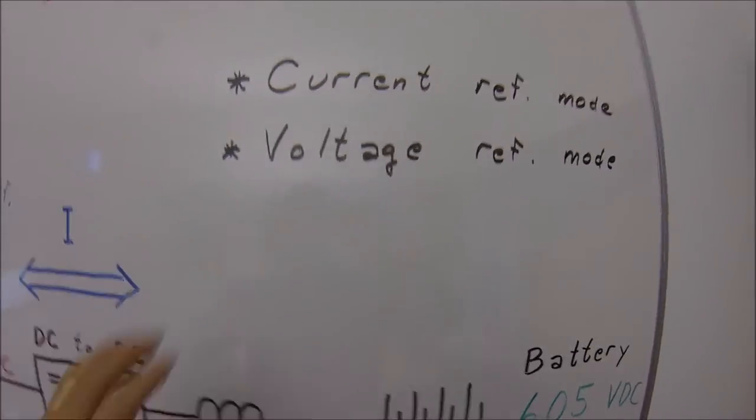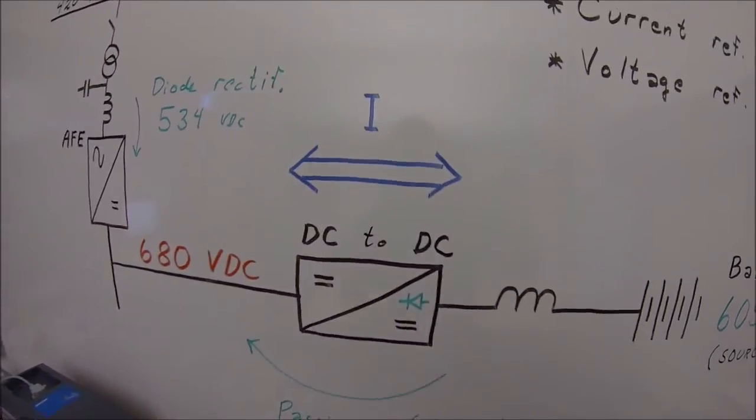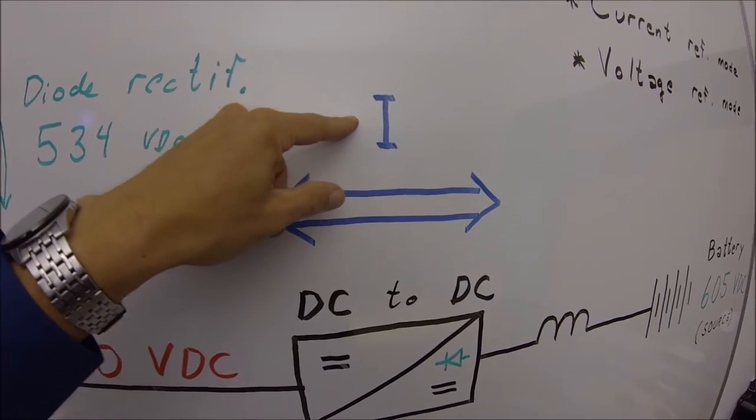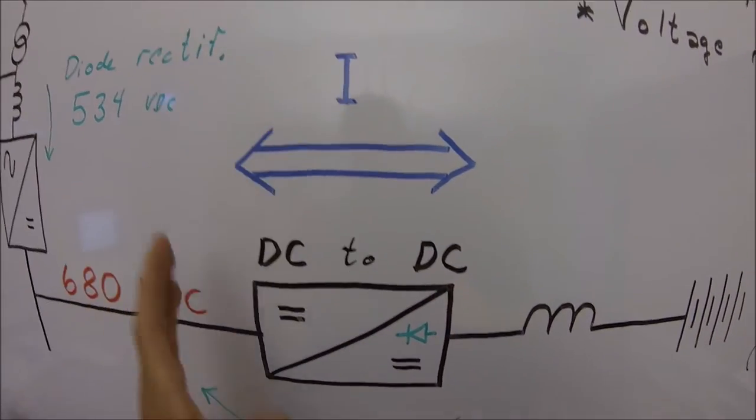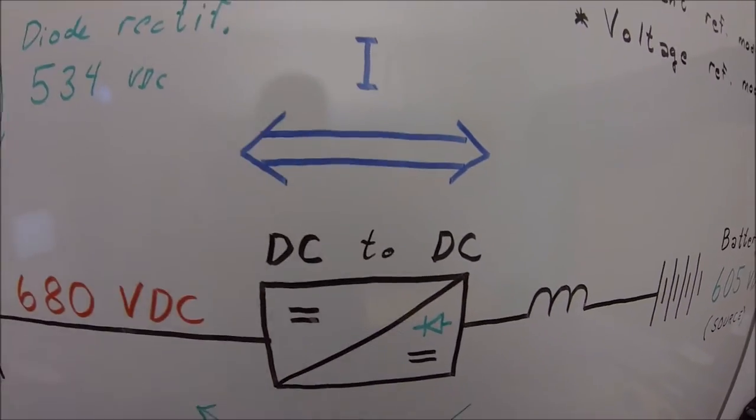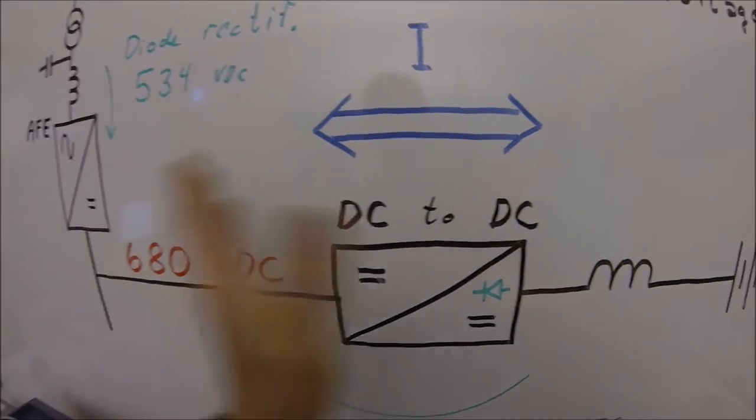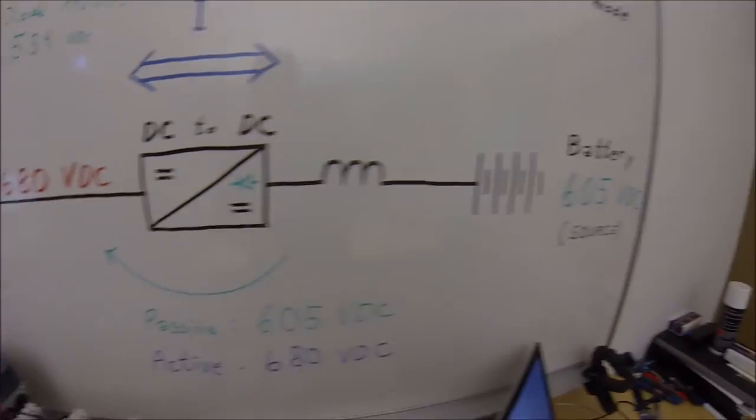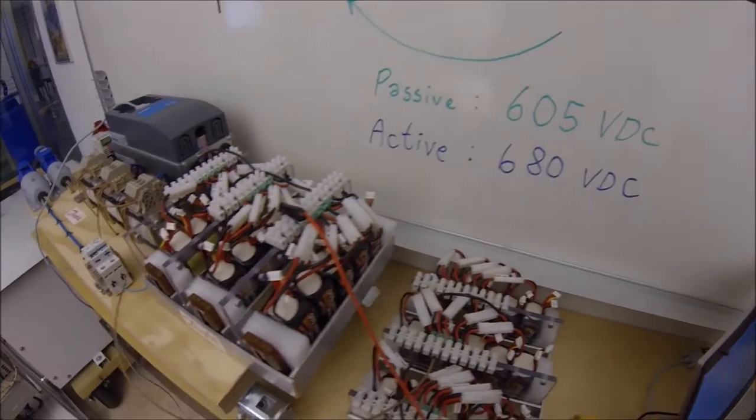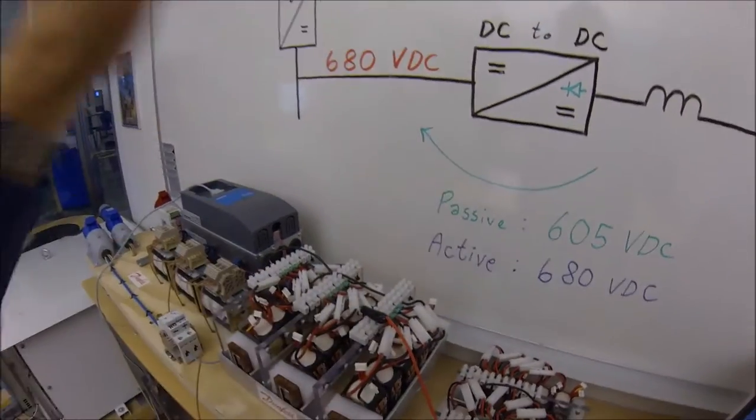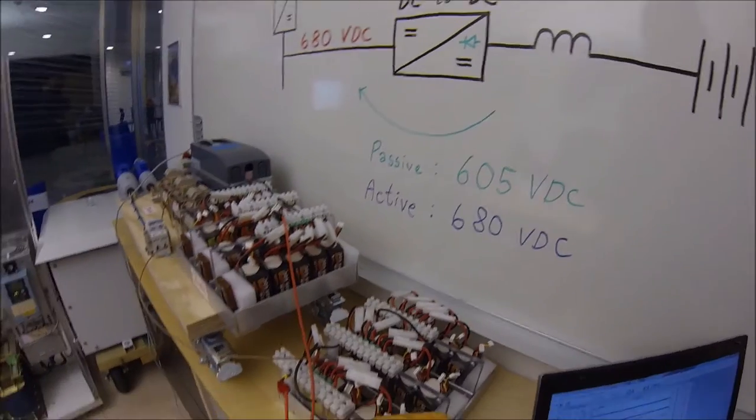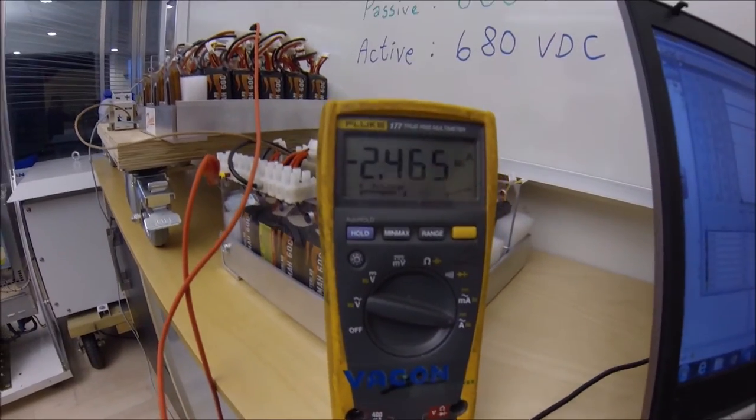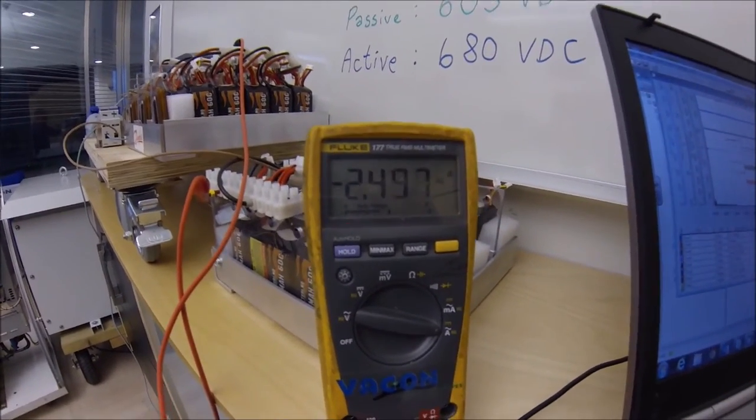When you are running the voltage reference mode, it could be a good idea to have current limits on how maximum charge and discharge currents will be allowed. Because if you have a battery with quite low impedance, then the current could be quite abrupt, big.